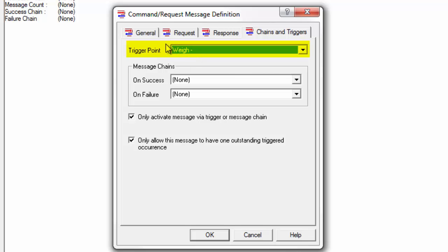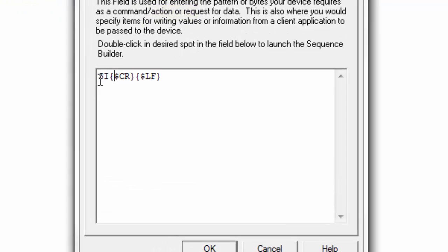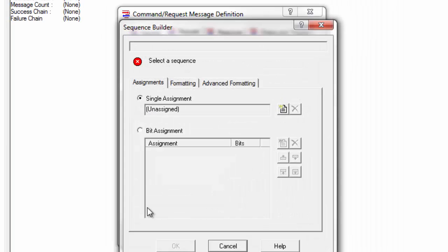Currently the trigger point on this is an item named 'Weigh'. This command is only ever going to get sent if you write a logical true or one to this item from your client application. If we go to the request section, this is the command that's actually being sent to the device. Since the commands are just ASCII characters, you'll see there's just a capital S and a capital I typed in here, and then we have a carriage return and a line feed, which is our special syntax in Omni Server.